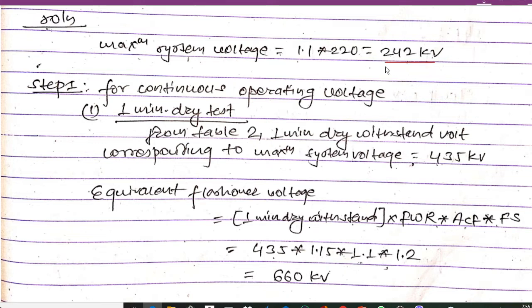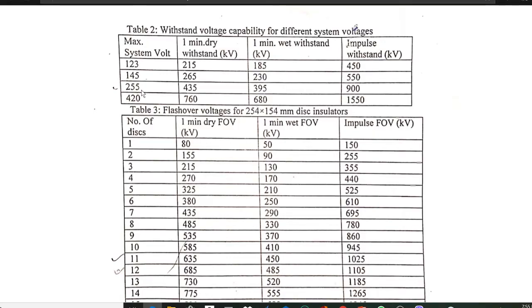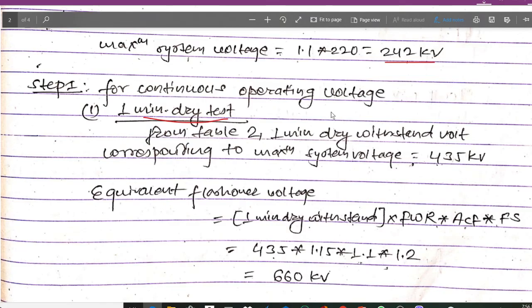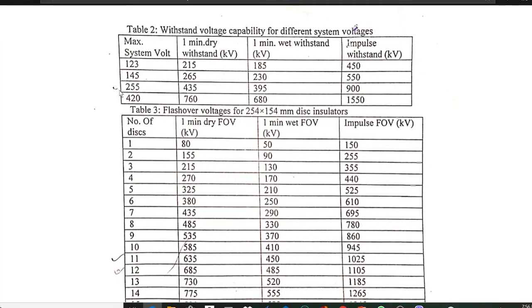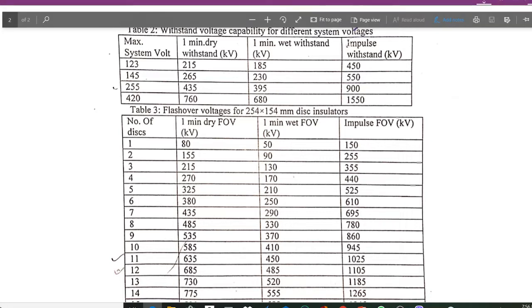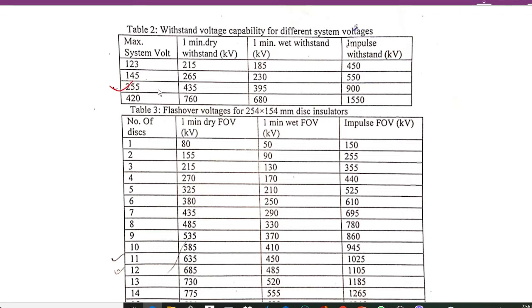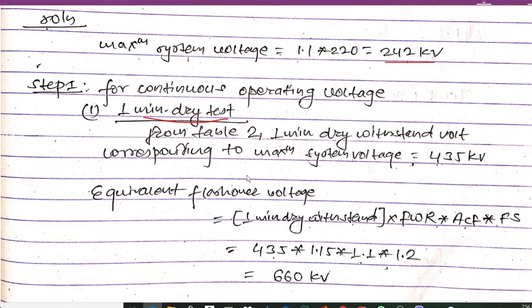In Step 1, for continuous operating voltage and one-minute dry test: from Table 2, the one-minute dry withstand standard voltage corresponding to maximum system voltage is 435 kilovolt. From the table, the maximum system voltage is 242 kV, and the next standard value above that is 255 kV. Corresponding to 255 kV, the one-minute dry withstand standard voltage is 435 kV, the one-minute wet withstand standard voltage is 395 kV, and the impulse withstand standard voltage is 900 kV.